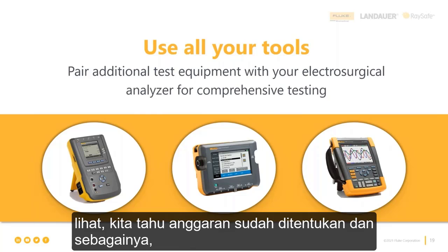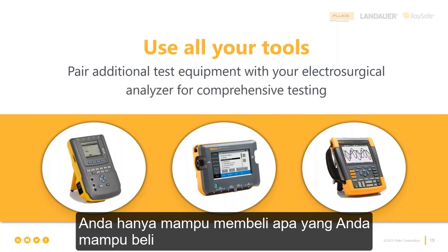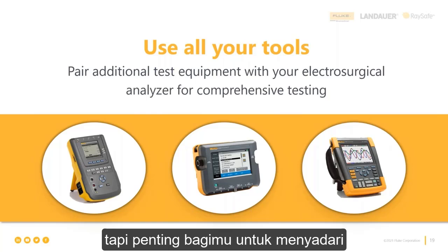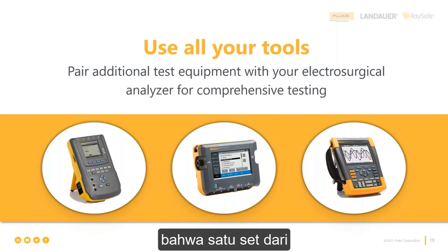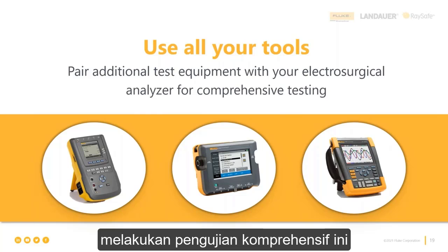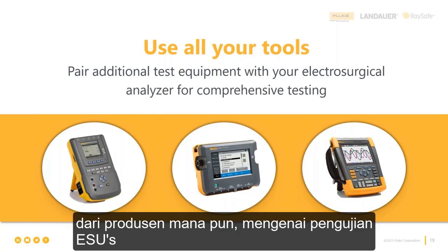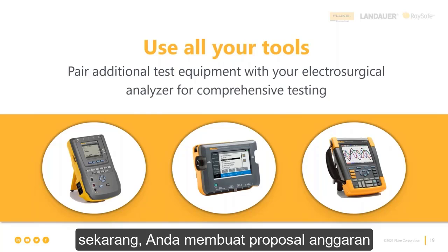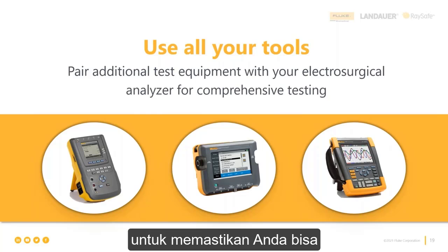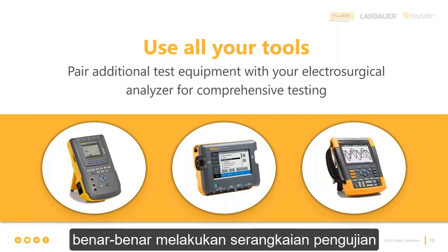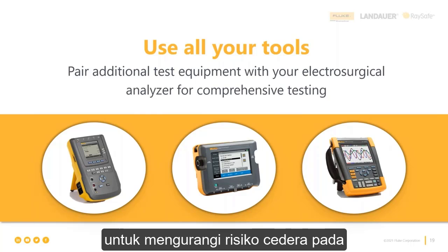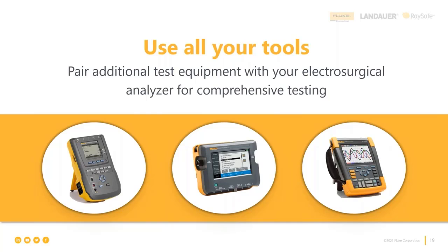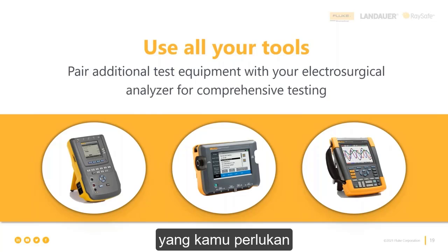All right. So look, we know budgets are budgets, and you can afford what you can afford, but it's important that you realize the set of test instruments that you need to do this comprehensive testing in order to get through any workflow from any manufacturer about ESUs. So if you don't have it now, be sure that you're making the budget entries and acquiring these categories of test instruments to make sure you can actually do the full array of testing that needs to be done to reduce the risk of injury to the patient, ensure proper clinical effectiveness of the functionality of the ESU, and collect all of the information that you need.